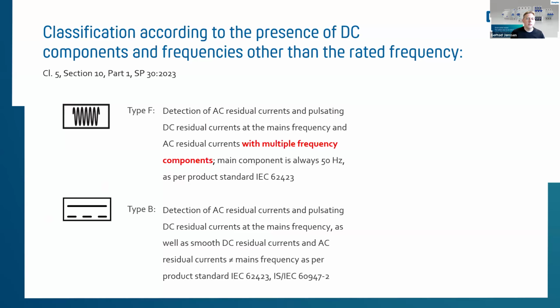But if it comes to industrial protection or industrial applications with three-phase loads, the next RCD category is coming into account. It's called type B. So it's as well capable of A, AC, and F residual current. But the main thing for type B RCCBs is that it's capable of smooth DC residual currents or direct DC residual currents. So that is the one and all best solution to detect each and every kind of residual current. In Germany, we even call it all current protection. It's not the right translation, I know that, but it's known as that.